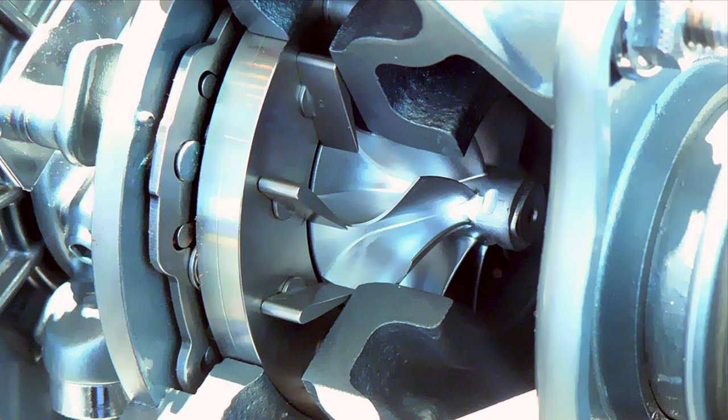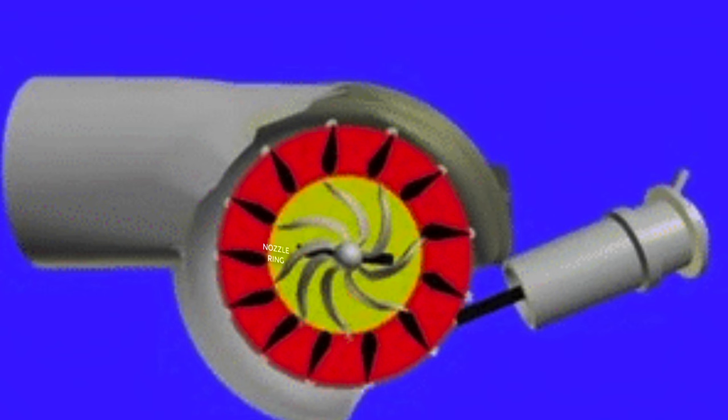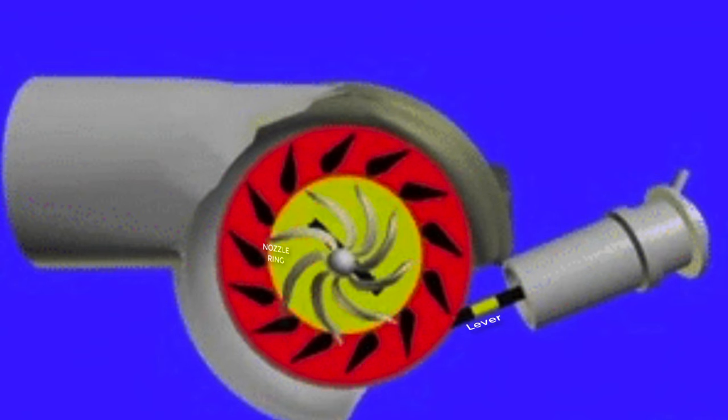The VGT or VTA consists of nozzle rings which are equipped with adjustable angle changing vanes. Each vane is connected to control ring using a lever which reduces the thermal hysteresis and increases the positional accuracy.